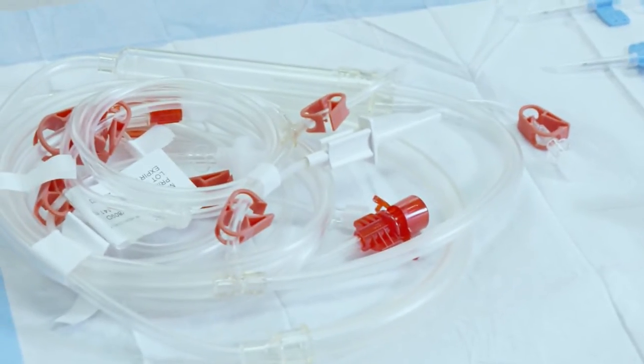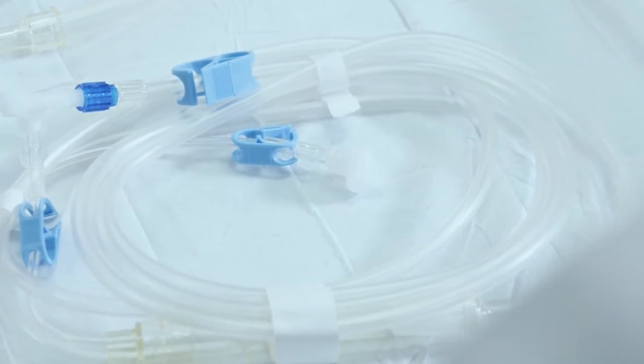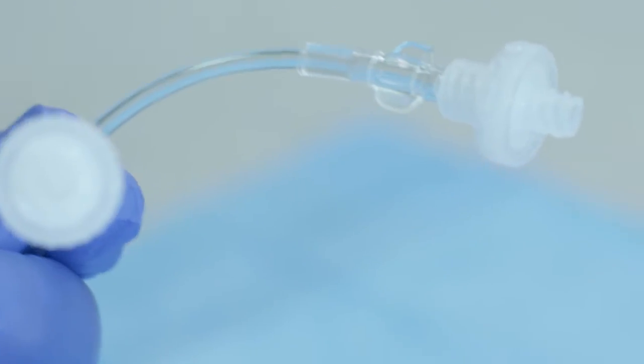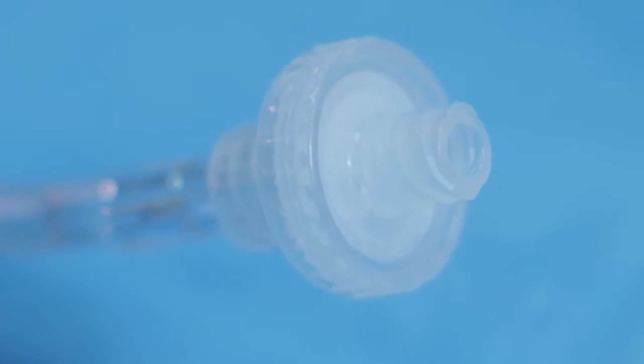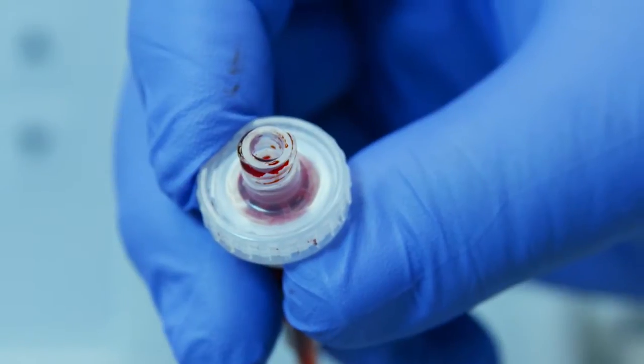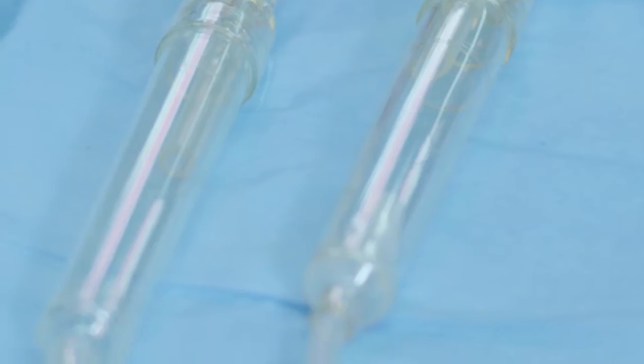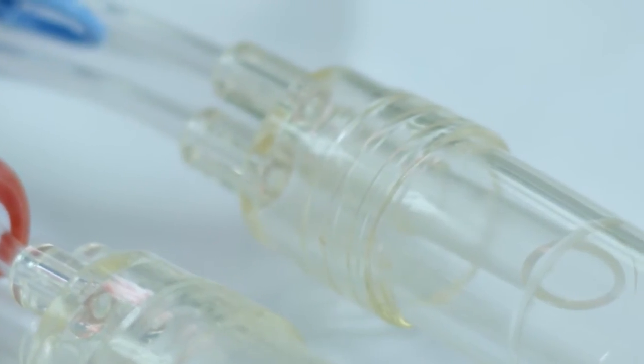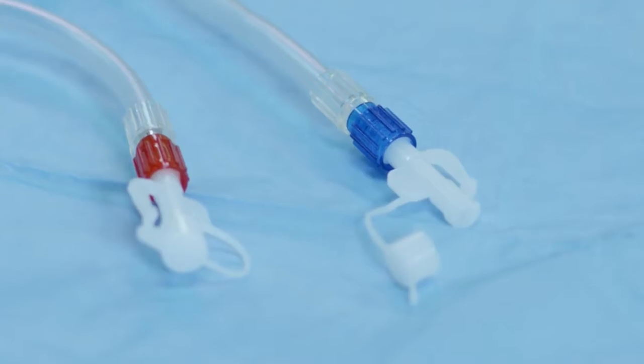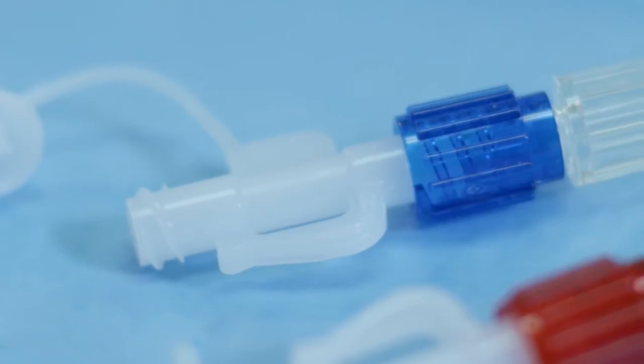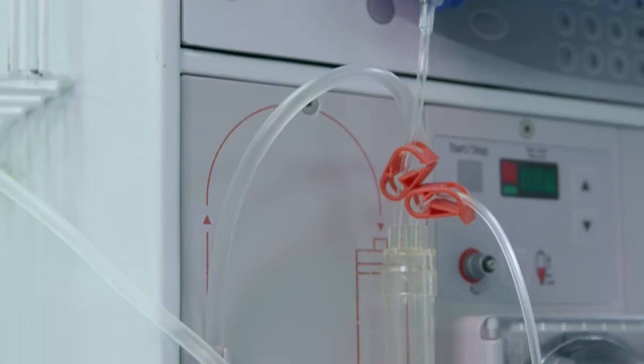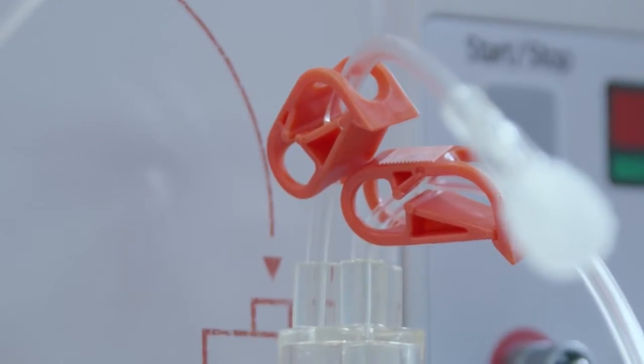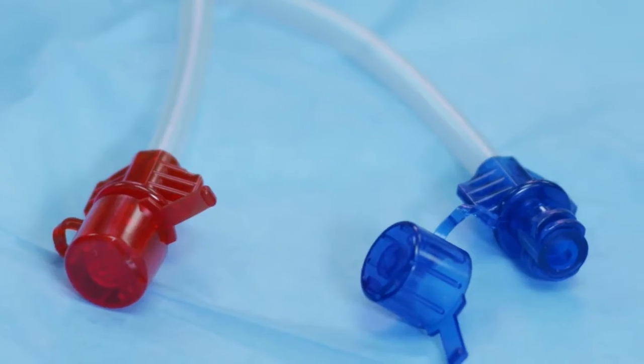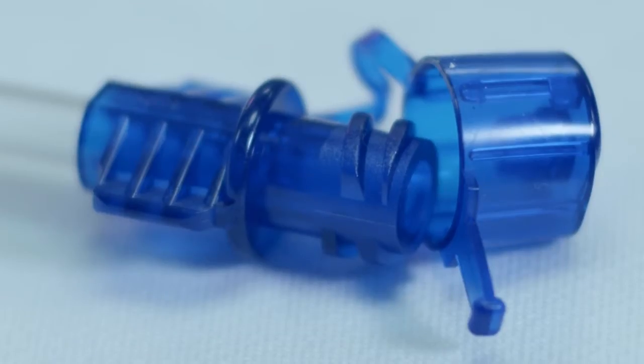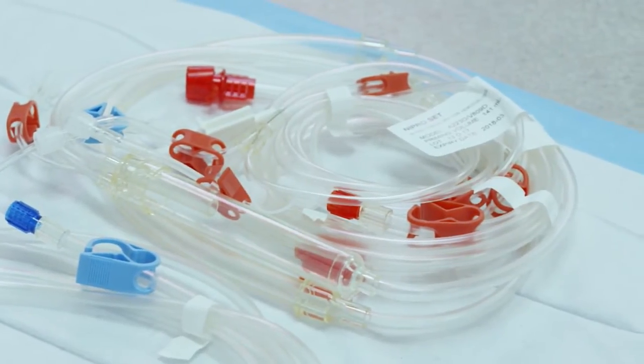Clamps are color-coded for confident identification of the appropriate line. Transducer protectors are clear throughout to allow easy identification of any cross-contamination. Drip chambers are anti-foaming to minimize splashing. Vented recirculation caps allow priming of the extracorporeal system while maintaining a sterile environment. The NiproSet also includes vented dialyzer caps, a spike cap, and permanently attached IV priming set.